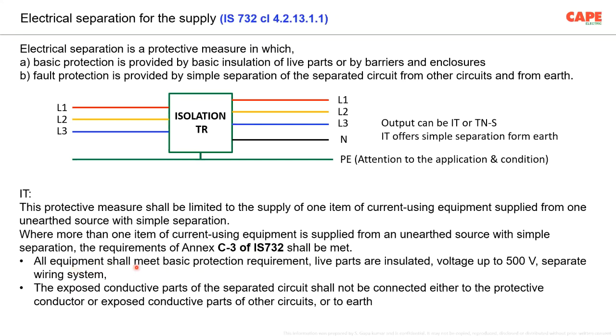For example, all equipment meets the basic protective measure, live parts are insulated completely, and it can be applied for voltage up to 500 volt. A separate wiring system is required. If you are not using a separate wiring system, then you have to take care of some of the mechanical damages which may arise, and special requirements are there. The exposed conductive part of the separated circuit shall not be connected either to the protective conductor, or exposed conductive parts of the other circuits, or to the earth.